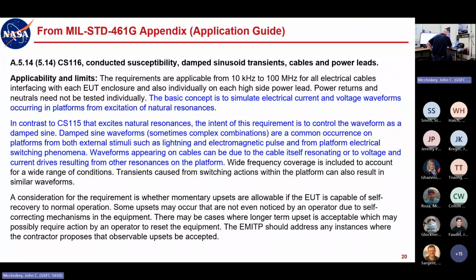In contrast to CS115 that excites natural resonances, the intent of this requirement is to control the waveform as a damped sine. Damped sine waveforms, sometimes complex combinations, are a common occurrence on platforms from both external stimuli, such as lightning and electromagnetic pulse, and from platform electrical switching phenomena. Waveforms appearing on cables can be due to the cable itself resonating or to voltage and current drives resulting from other resonances on the platform.